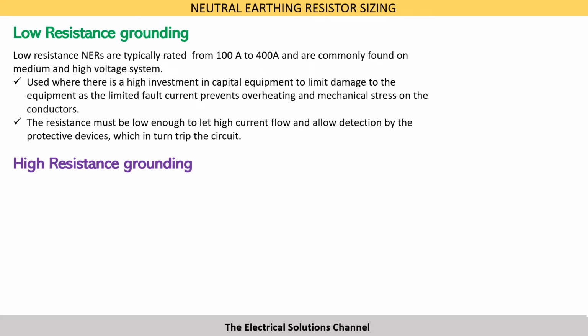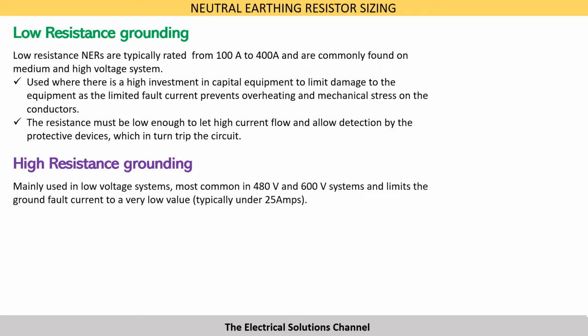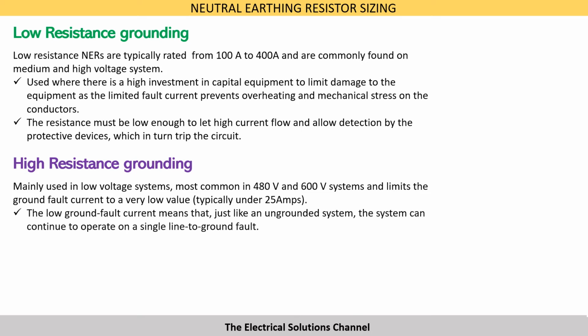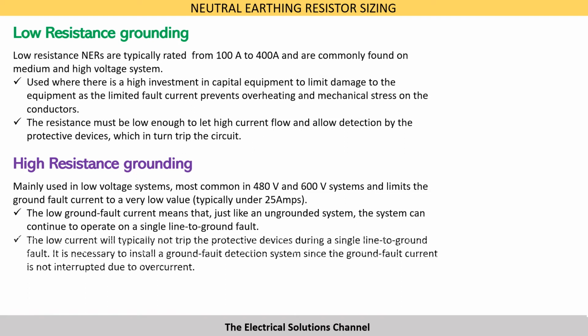Whereas the high resistance grounding is mainly used in low voltage systems, most common in 480 volt and 600 volt systems, and they limit the ground fault current to a very low value, typically under 25 amps. The low ground fault current means that just like an ungrounded system, the system can continue to operate on a single line to ground fault. The low fault current will typically not trip the protective devices during a single line to ground fault.